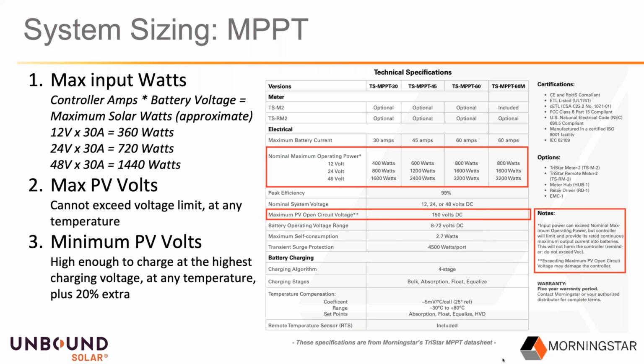In Morningstar's case, they have this on their data sheet, so all you have to do is look at their data sheet, and it also has a note that you can actually overload the controller, and it's going to limit to these values. So you can actually put in a larger solar array, and it's obviously going to limit the current output.